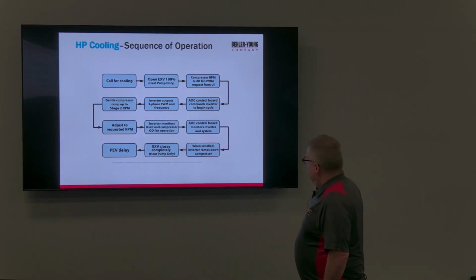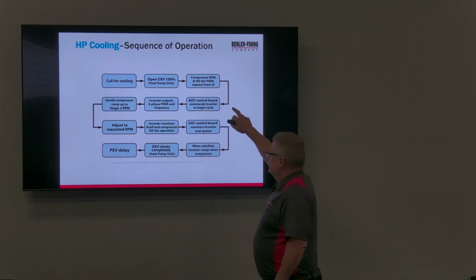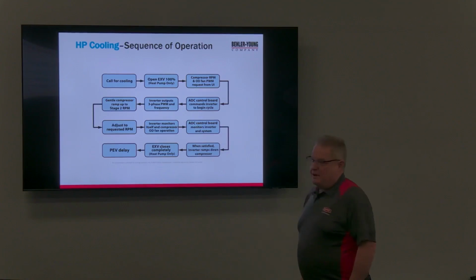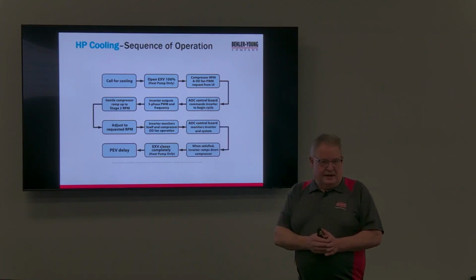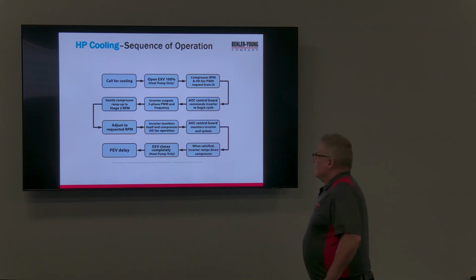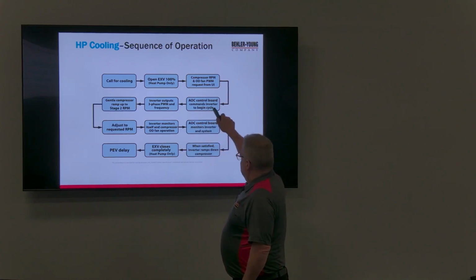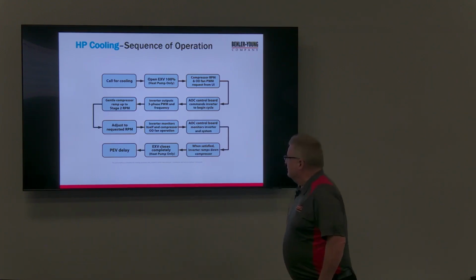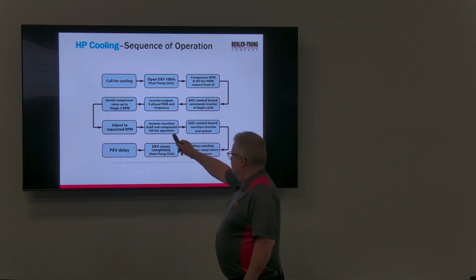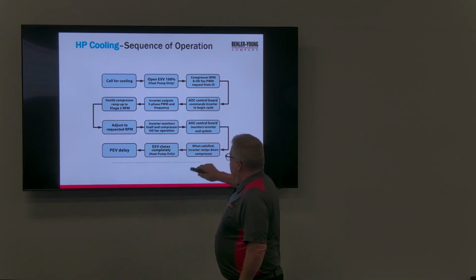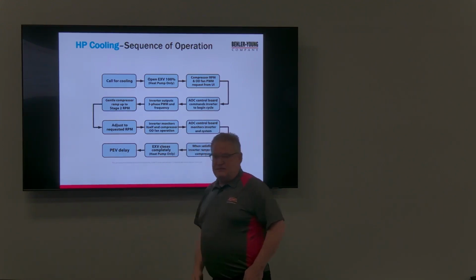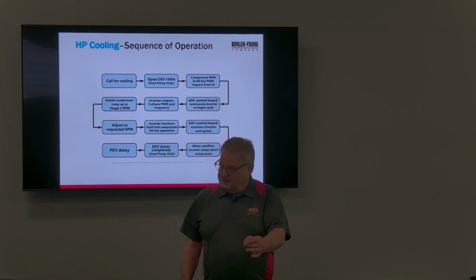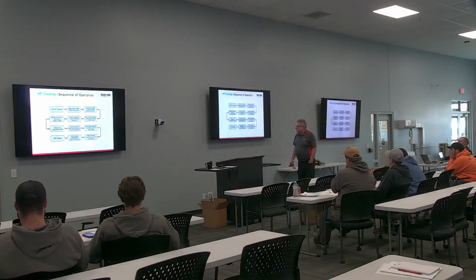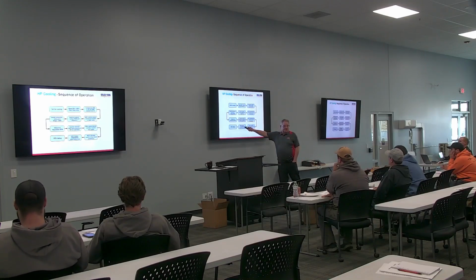Okay. Compressor RPM and fan motor request from the wall control is going to tell it what to do. Compressor is going to ramp up in stages. Again, on the 288 or the 189, it'll ramp up. It's 5 steps. 284, it's going to ramp up slowly. All right. It's going to level itself out. The AOC control board commands the inverter to begin the cycle. It's going to adjust the RPM as required. The inverter monitors compressor speed and outdoor fan operation through the whole run. When we're ready to shut down, the equalizer valve, you'll notice there's a valve sitting on the top. It equalizes the pressure when it shuts down to allow the system to equalize out. The EXV in the outdoor unit closes completely.